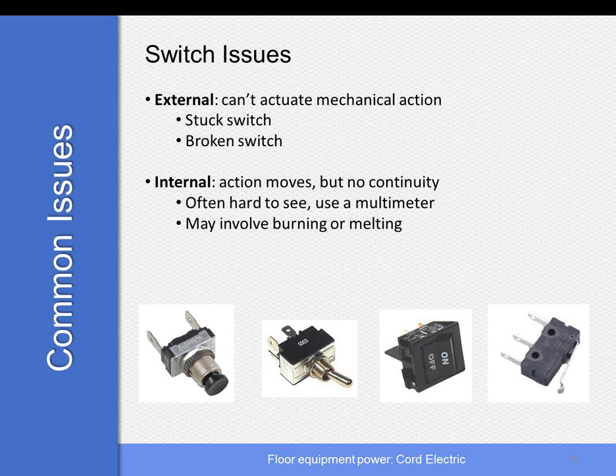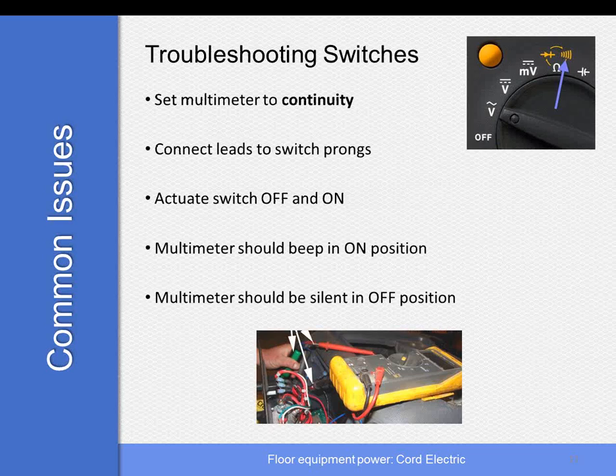That's going to be hard to see because if the break is internal, you'll need the multimeter to probe your ends to check for continuity. Sometimes you have burning that you can't see from the outside. It'll burn on the inside, and that'll ruin your continuity as well. So to troubleshoot, you're going to set your multimeter to continuity. That's the symbol that looks like a couple curved lines in ascending order.